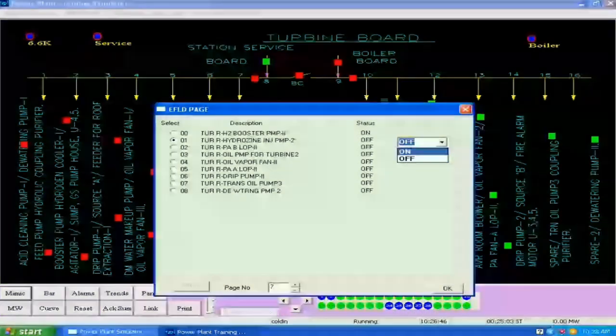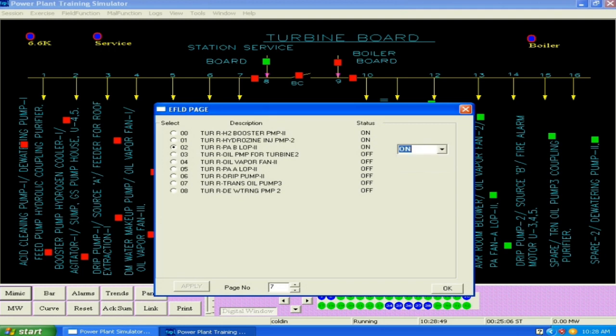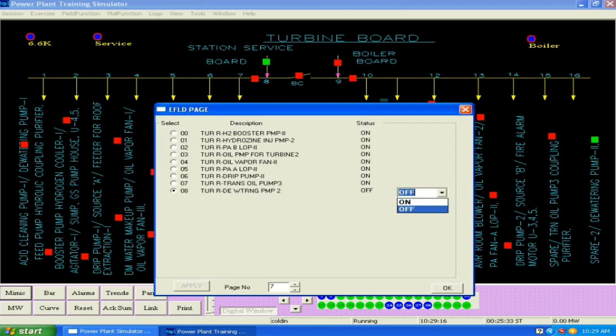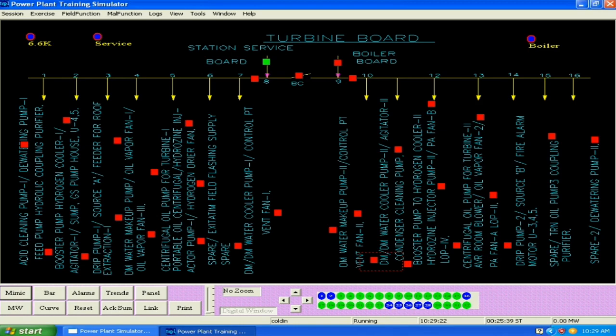On E field page number 7, from 00 to 08 means the H2 booster pump, hydrogen injection pump, then PA B LOP2, then oil pump for turbine, oil vapor fan, PA A LOP2, drip pump 2, then transformer oil pump 3, dewatering pump 2. All these supplies are to be made on, and once you make this on, you will see that the turbine board has been charged completely. You will be able to see that all the indications are red now, so they are on.